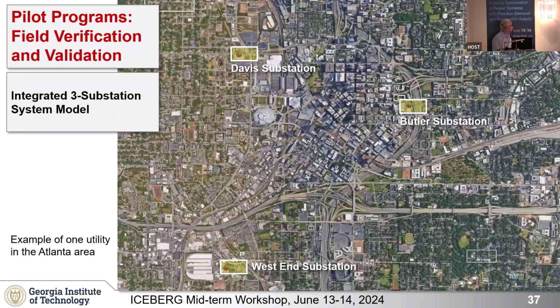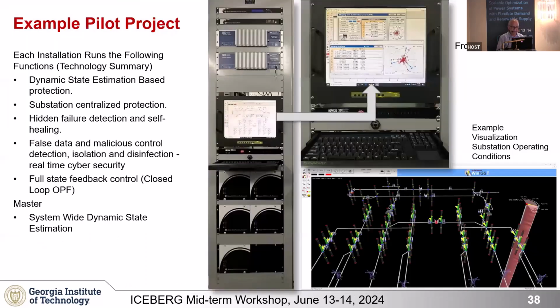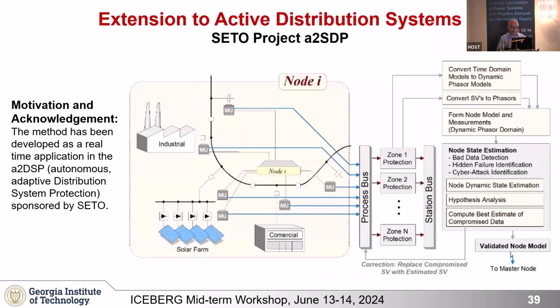Here are some installations very close to Georgia Tech. We have 3 substations implemented with this — we call this the digital substation. You can see the installation here, some of the user interfaces, visualizations of the state estimation results, and the merging units installed. As a matter of fact, with this system I don't have to have a big control house for the substation — a small control house can house all of this. So it's also an issue of volume, I guess.